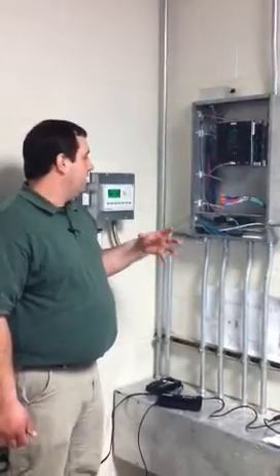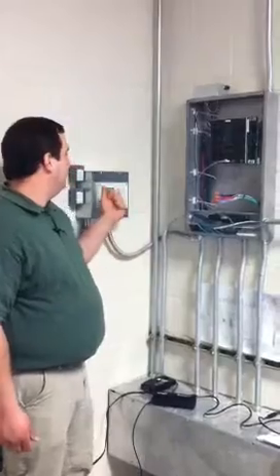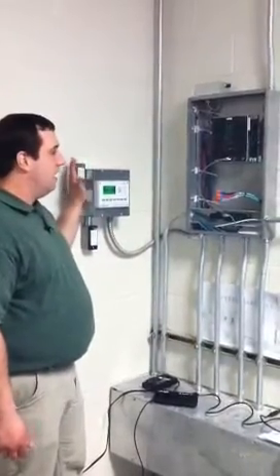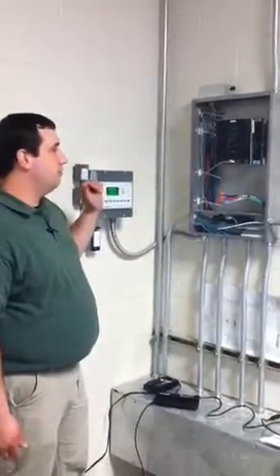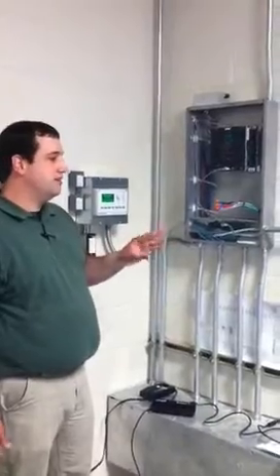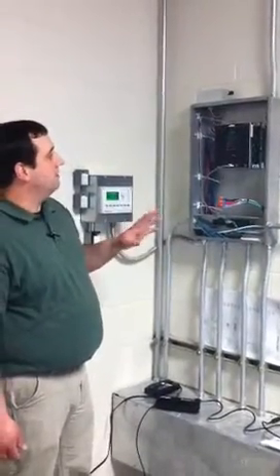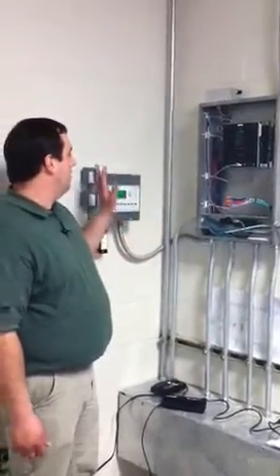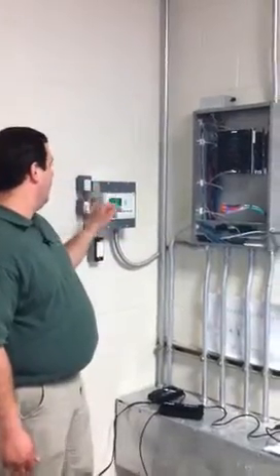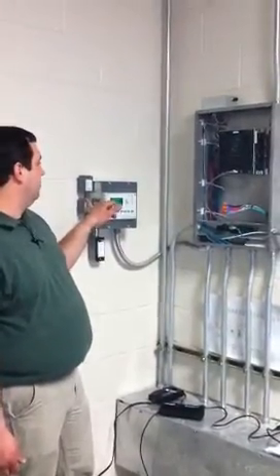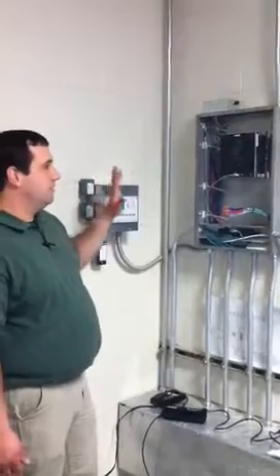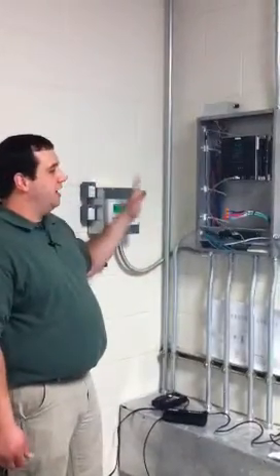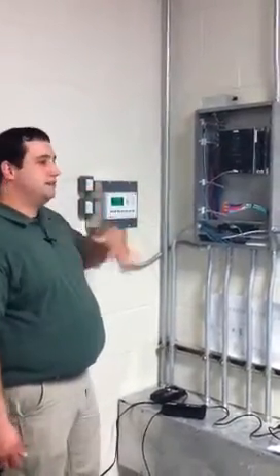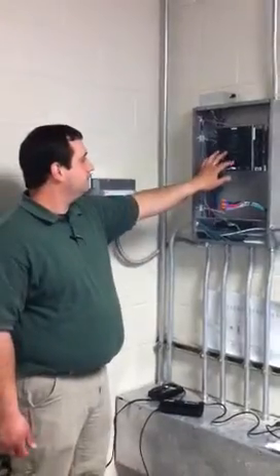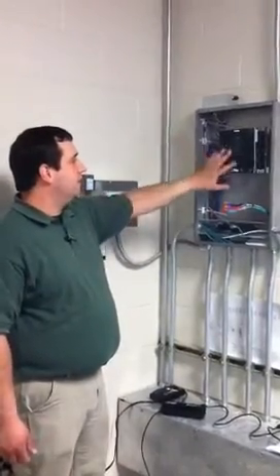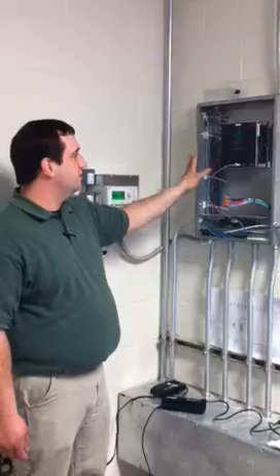The other thing is that there are two BMS interfaces into it. There's one for interior, so it's all interior lights on, all interior lights off, all exterior on, all exterior off. Those are triggered separately from that, and those have pilot lights on the individual relays themselves. So if, for example, those are on and you can't turn the lights off, it's possible the BMS system has overridden the system. On the front of the unit, there's really nothing to PM, there's nothing to service.